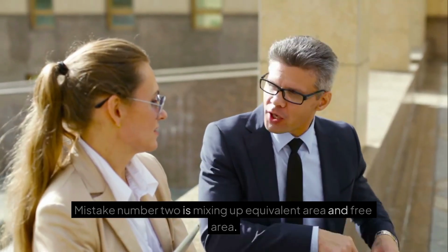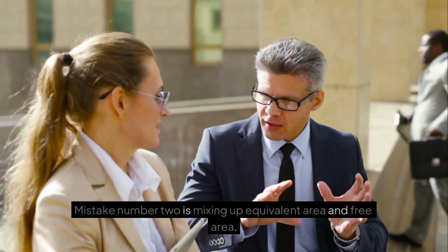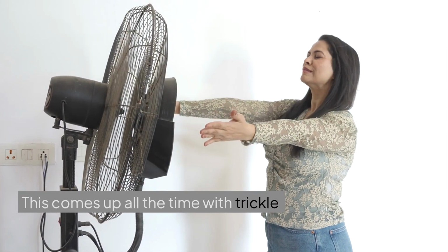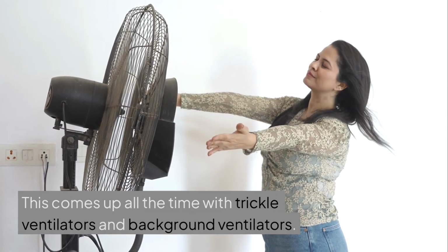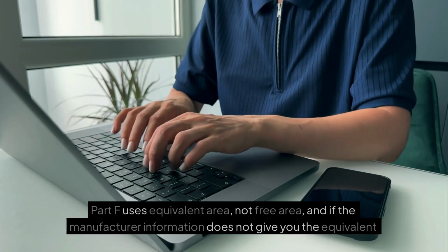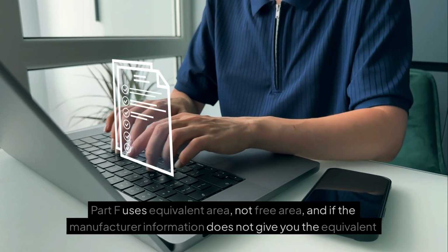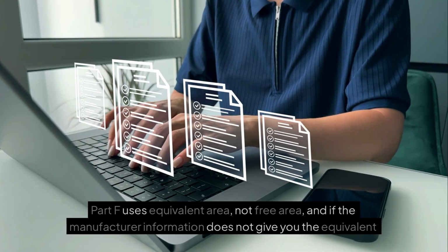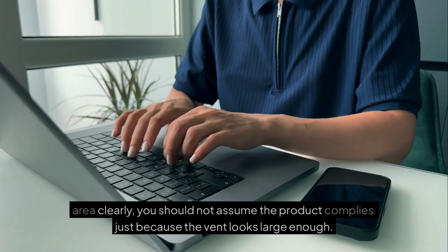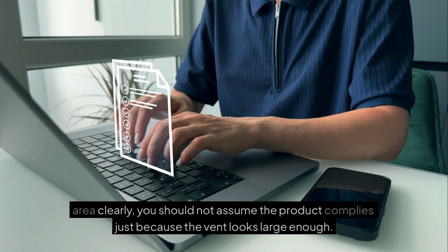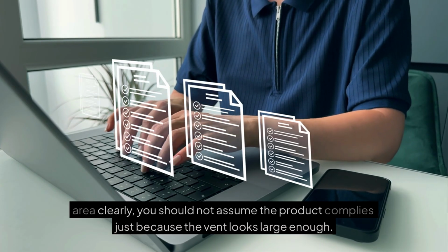Mistake number 2 is mixing up equivalent area and free area. This comes up all the time with trickle ventilators and background ventilators. Part F uses equivalent area, not free area, and if the manufacturer information does not give you the equivalent area clearly, you should not assume the product complies just because the vent looks large enough.